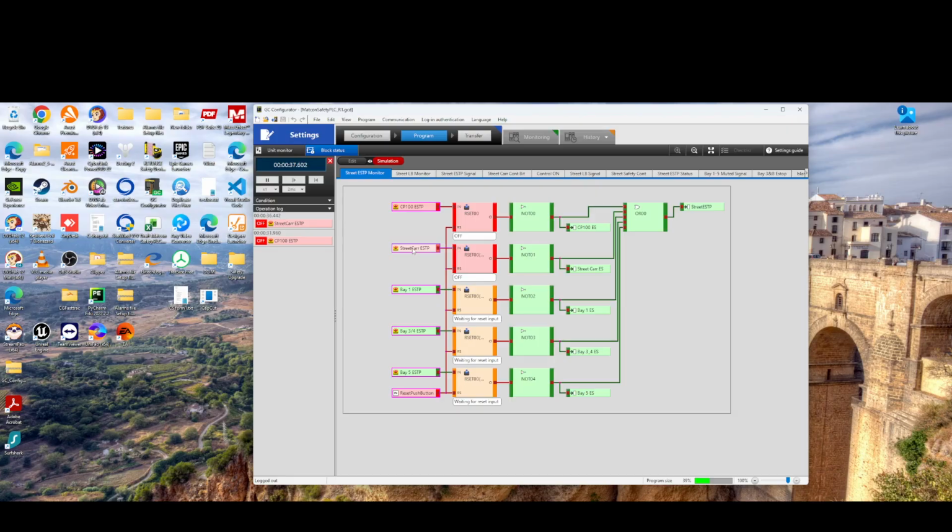We're going to come here, and here, and here, and here, and we're going to hit the reset push button, and nothing happens. You can see I'm hitting the reset, and nothing is happening. So now I'm going to go back and make these true again, which says that the actual inputs are true. And now I'm going to hit the reset button.